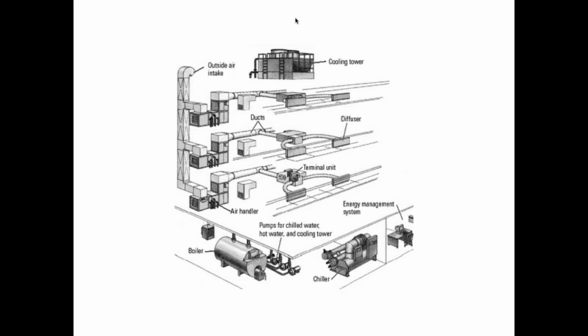So what would you say is one of the important things about where you locate a cooling tower in a building? Where do you not want to put a cooling tower? No, not the basement so much, but yeah, your basement's a bad spot for it. I'll tell you why in a second. But no, in general, what's the one spot that you don't want to put it next to? Remember our ductwork there, our exhaust duct? You don't want it near the fresh air intake. If it's near the fresh air intake, anything that's in those droplets can get sucked into the building.